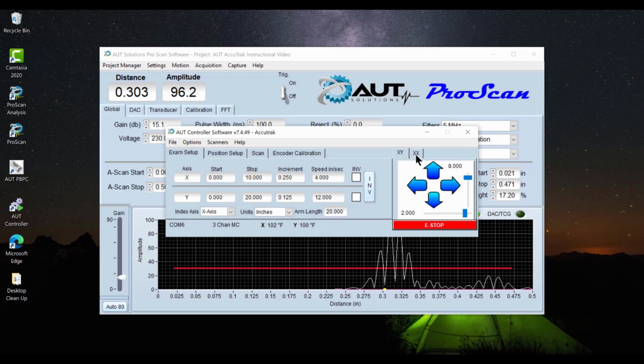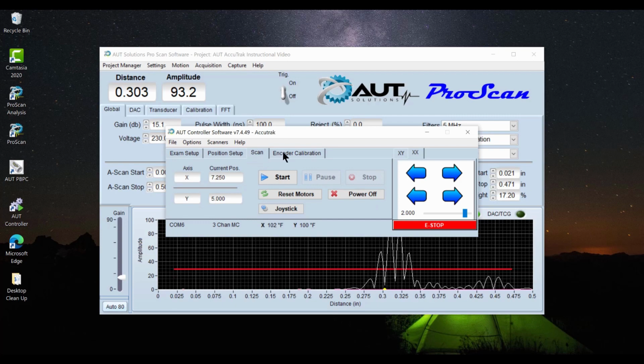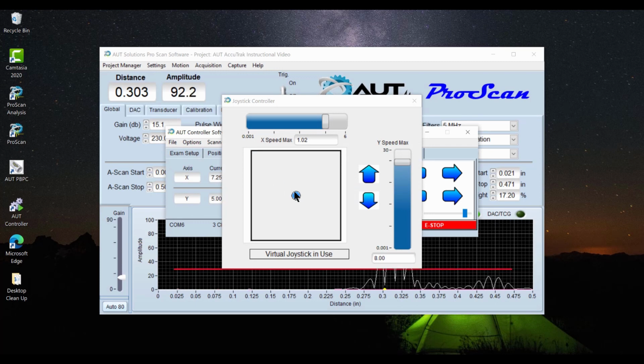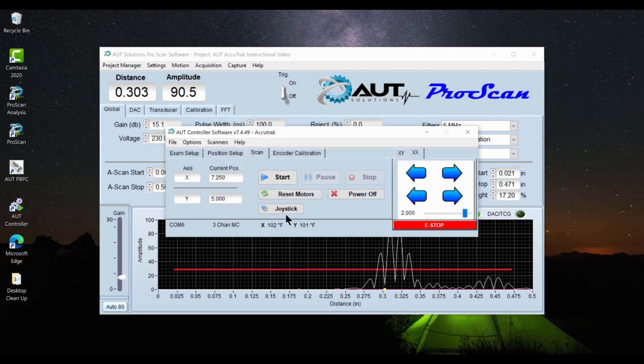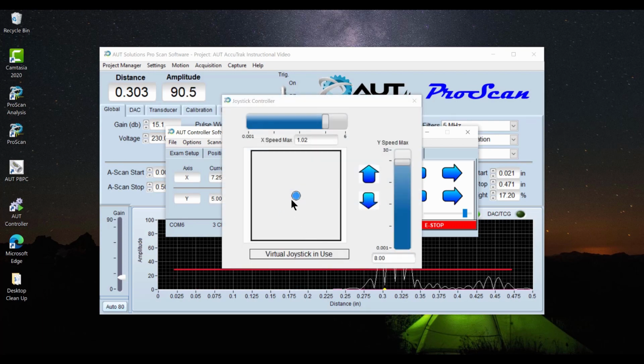Now with the AccuTrak, you'll have an additional panel here that will show you XX. This will give you the ability to steer the scanner automatically. So you have the left motor on top and the right motor on bottom. So you have the ability to steer each one of them independently. Now if you needed to move it a little bit more precise, you do have the option with the AccuTrak to click on joystick. It will give you a virtual joystick, which will then allow you to drag this blue dot. You can move it in any direction that you want. The scanner will also follow. If you need to move the Y arm, you would use these two buttons here. Just simply click and press, and they will move. So if you do have the Bluetooth joystick controller or a wired joystick, you could simply plug those in with this screen up, and it will not say virtual joystick. It will just say joystick in use, and you could use those to control the scanner as well.